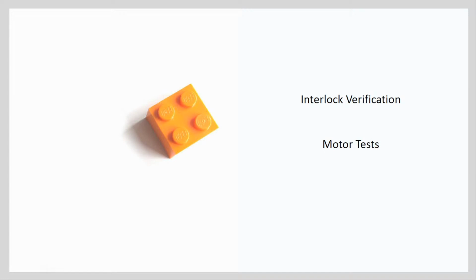So pre-commissioning is complete once you've completed all your checklists and verified that each piece of equipment meets the technical requirements of the project. During pre-commissioning, this is when the equipment is really tested standalone. It doesn't operate and function as a system quite yet. You're testing out each piece of equipment to confirm that it's ready for later commissioning during the commissioning phase. The components really start to come together as a system during the commissioning phase, which we'll leave now for another discussion. So those are some examples of pre-commissioning activities that would be typical on an electrical project. There would be others as well, but those are some of the typical ones.